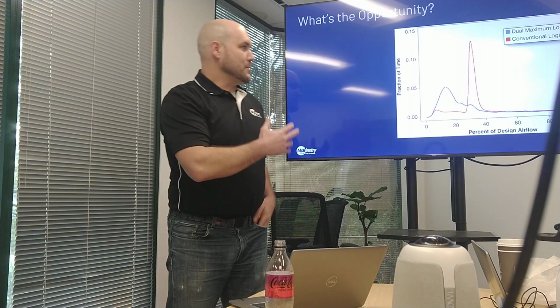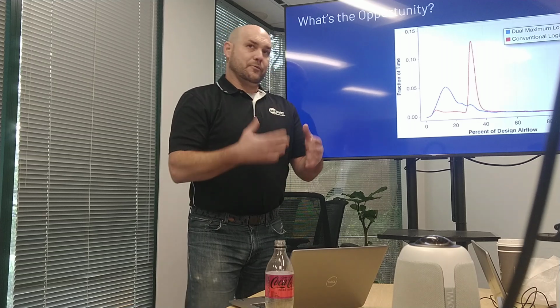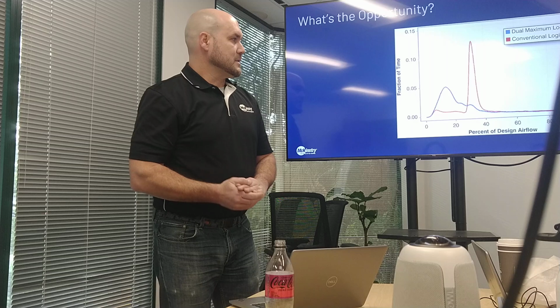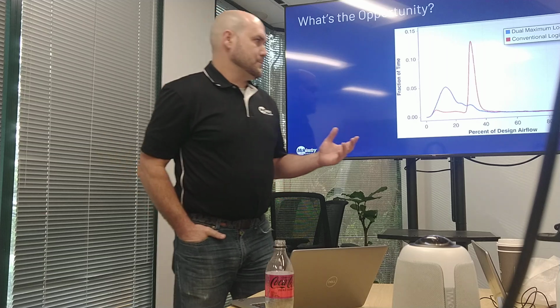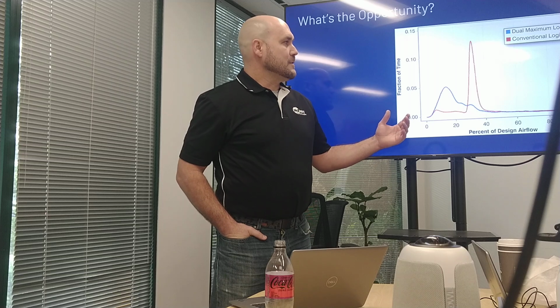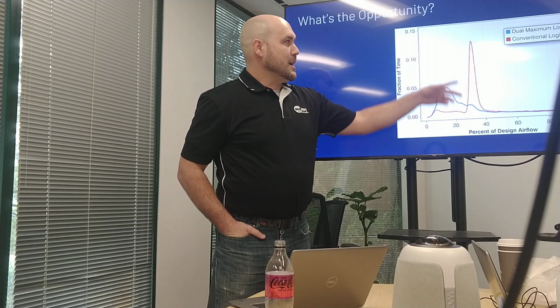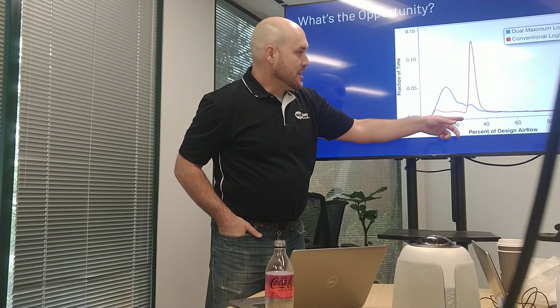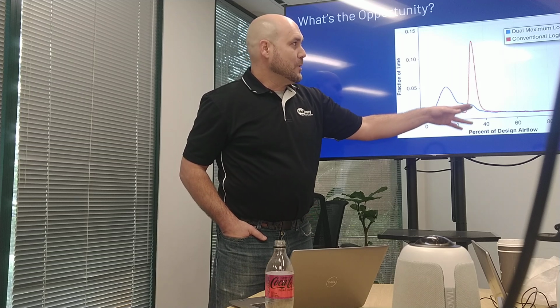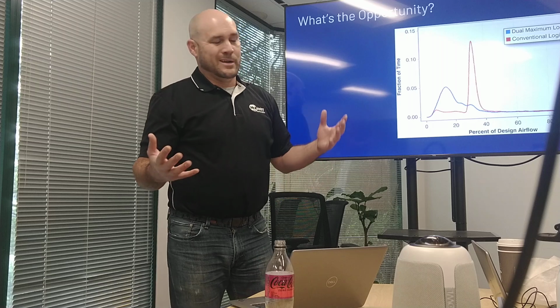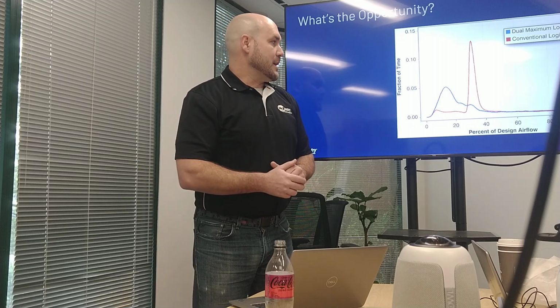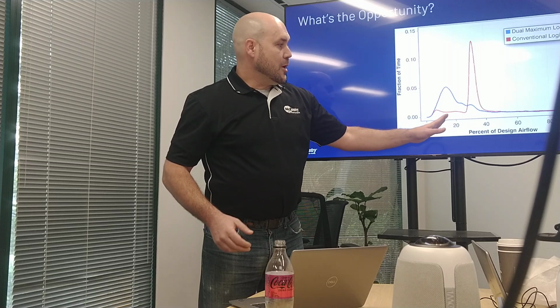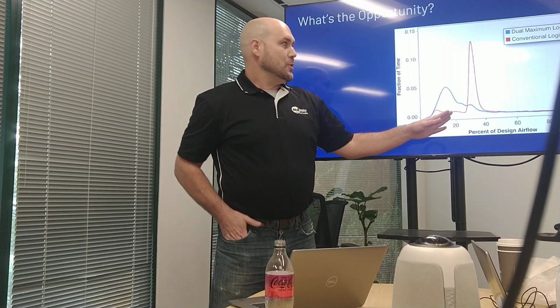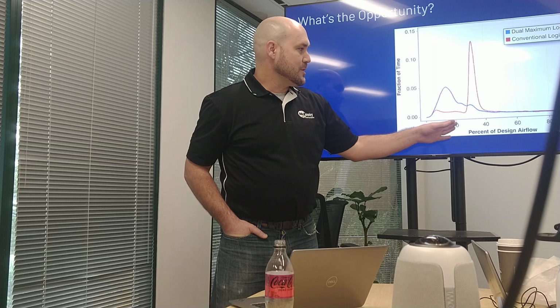I didn't do this study. This is something published by ASHRAE that was part of the research that went into ultimately the Guideline 36 publication. What you can see is conventional VAV logic. Most of the time, VAVs spend their time in the 30 to 40% of their design airflow. With what is called dual maximum logic, which is described and published in Guideline 36, that moves considerably lower, down below 20%. So it goes from the 30 to 40% window to the 10 to 20% window for the peak.